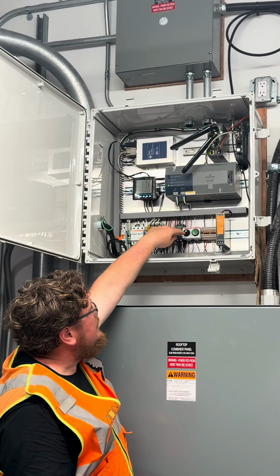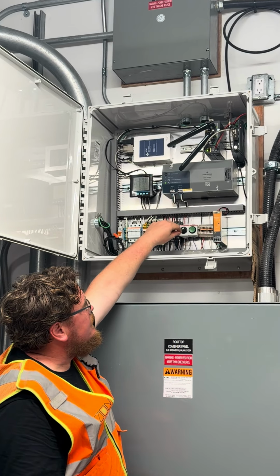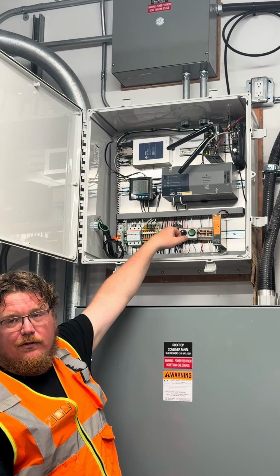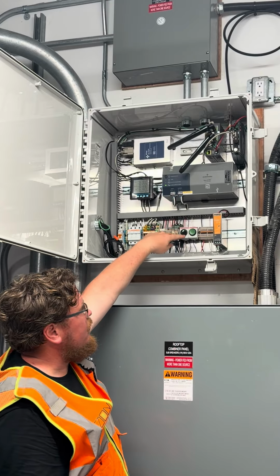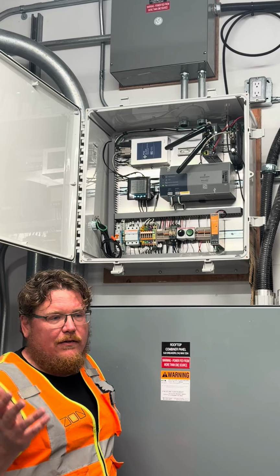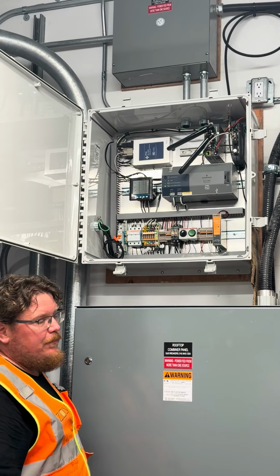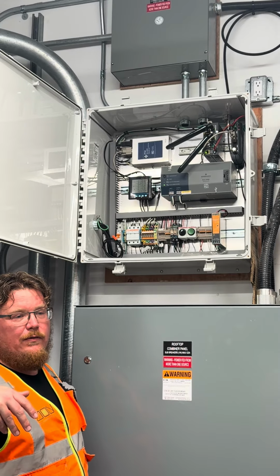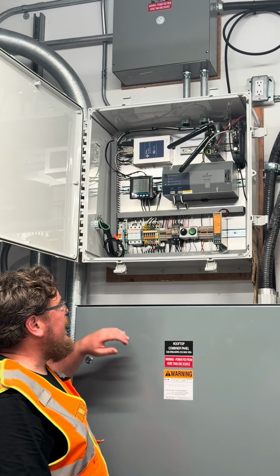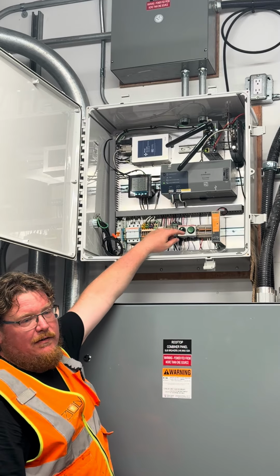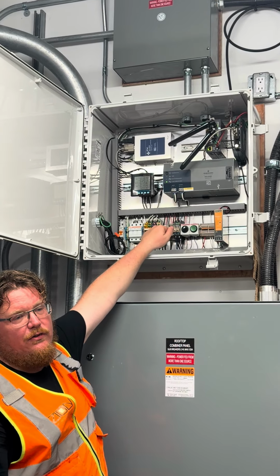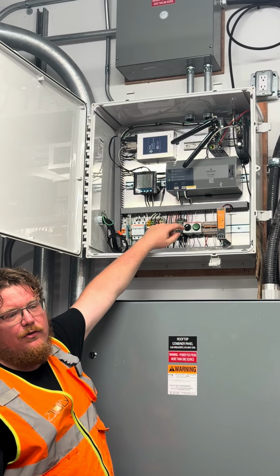If you do that though, when you turn it back on, there's a latching relay so it doesn't turn on automatically. You've got to push the green button and then it will connect and start operating. If Hydro One does a remote transfer trip on us, the only way to get the system back running is to turn that switch, turn it back on, and push the green button.